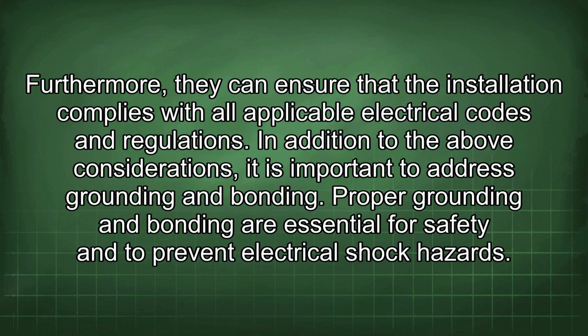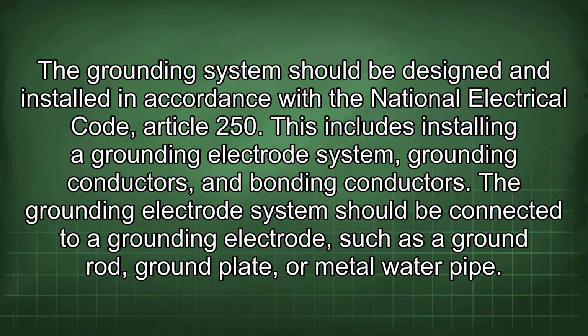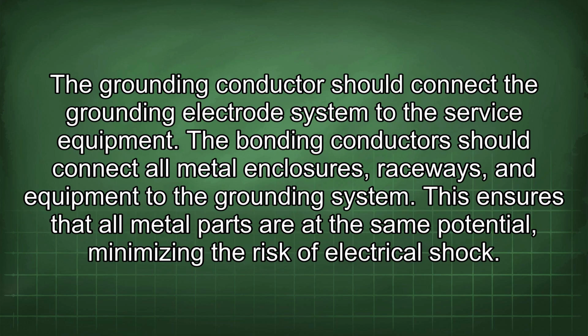In addition to the above considerations, it is important to address grounding and bonding. Proper grounding and bonding are essential for safety and to prevent electrical shock hazards. The grounding system should be designed and installed in accordance with the National Electrical Code, Article 250. This includes installing a grounding electrode system, grounding conductors, and bonding conductors. The grounding electrode system should be connected to a grounding electrode, such as a ground rod, ground plate, or metal water pipe. The grounding conductor should connect the grounding electrode system to the service equipment. The bonding conductor should connect all metal enclosures, raceways, and equipment to the grounding system. This ensures that all metal parts are at the same potential, minimizing the risk of electrical shock.